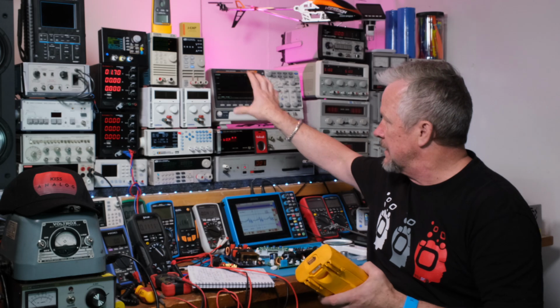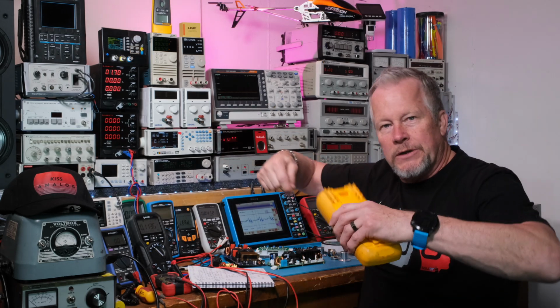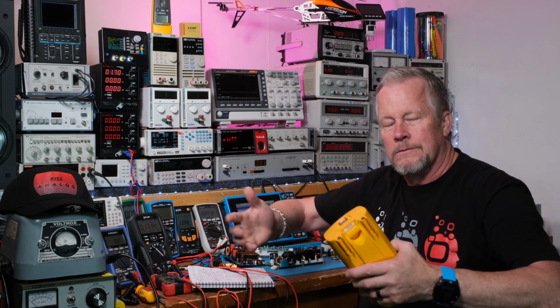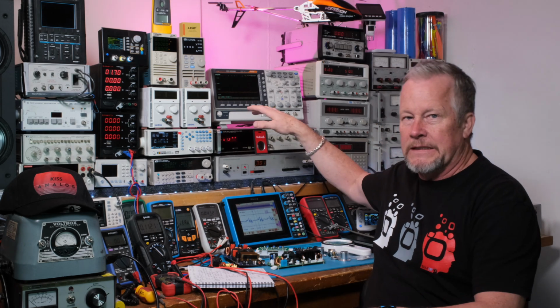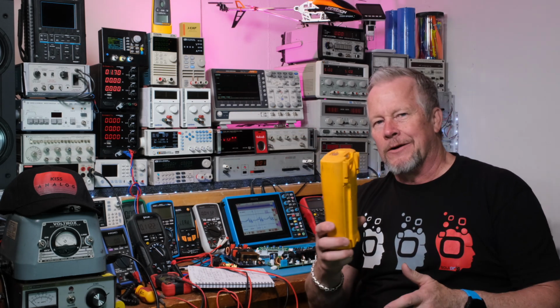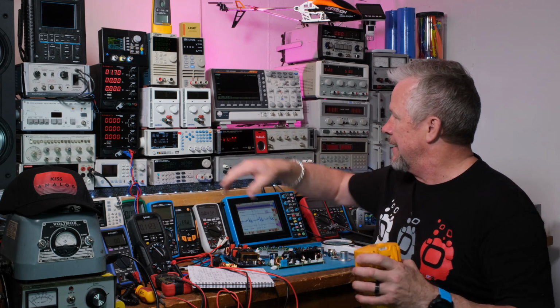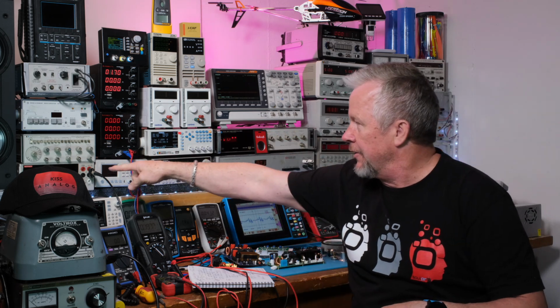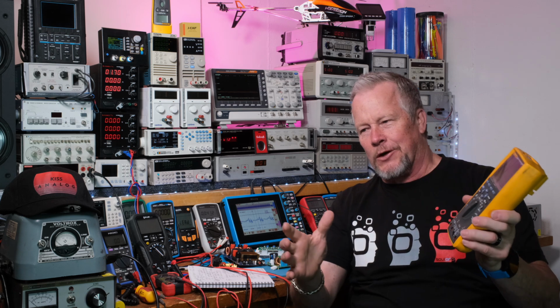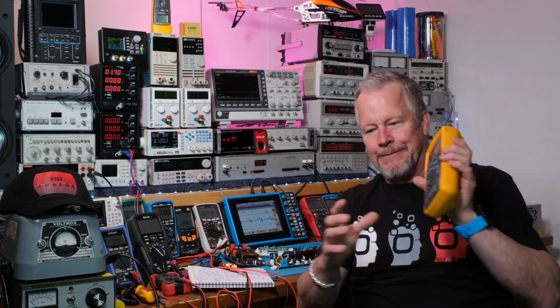That's Cat 2. If I open up this thing and do troubleshooting inside that, that's Cat 2. It's not Cat 3. It's not Cat 4. It's not the scary stuff. You have to be very careful. You can still die, right? But the meter is in a lot less trouble when you're doing this. As a matter of fact, if you look at your benchtop meters, look inside them. First of all, they're not rated for Cat 3, Cat 4. When you look inside, they don't have all those protective features either. Alright, guys, so I think the rant's over. I think I covered it.